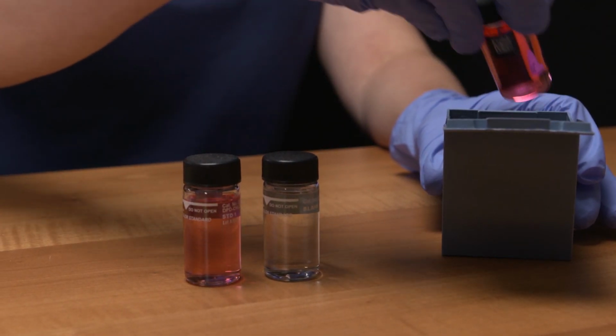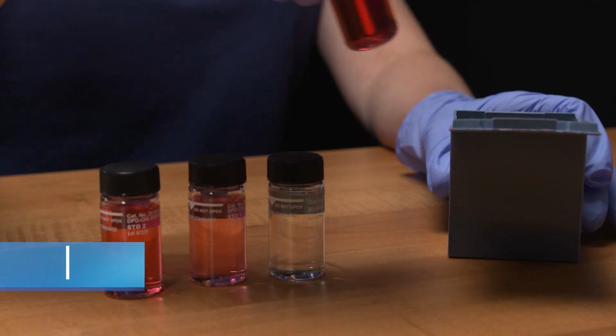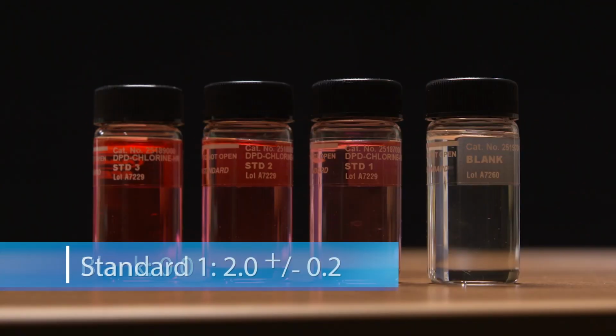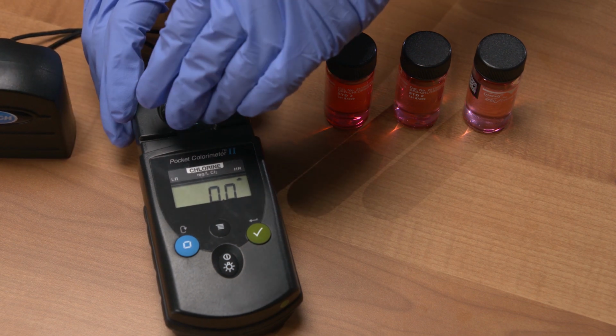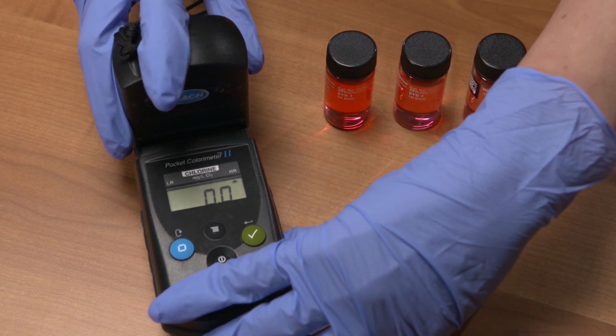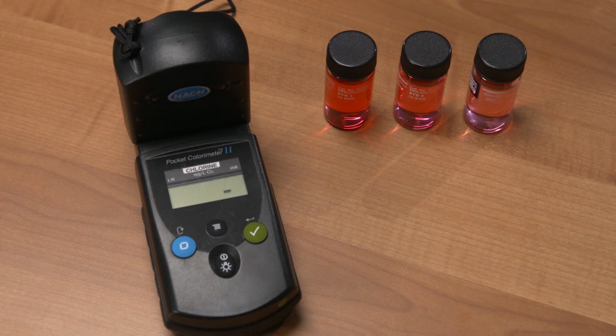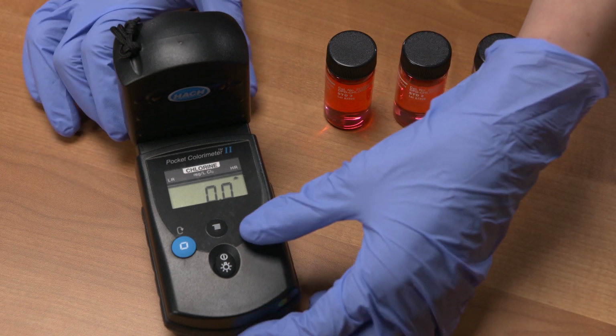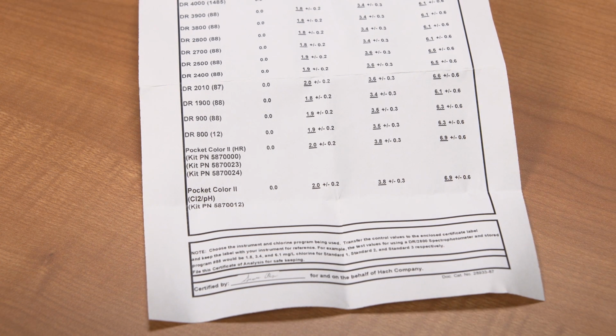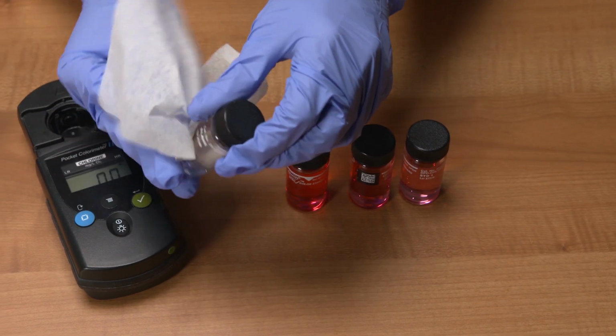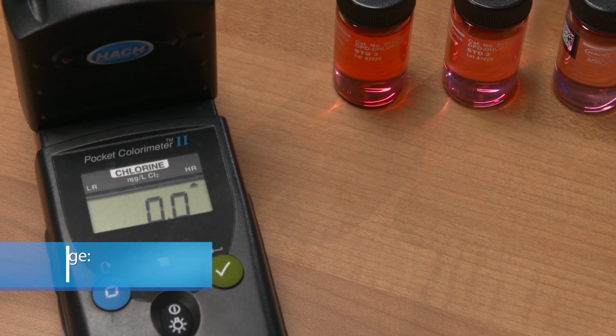Since we are using a Pocket Colorimeter II, the allowable readings for these standards are blank, 0.0, standard 1, 2.0 plus or minus 0.2, standard 2, 3.8 plus or minus 0.3, standard 3, 6.9 plus or minus 0.6. To perform a secondary verification, the meter should first be zeroed. Then we insert each standard vial into our instrument, wiping the vials before insertion, and write down the measurement. The measurement should be within the allowable range found on the certificate of analysis for your instrument. Wipe the standard vials before taking a reading to ensure that dirt and fingerprints do not affect the reading.